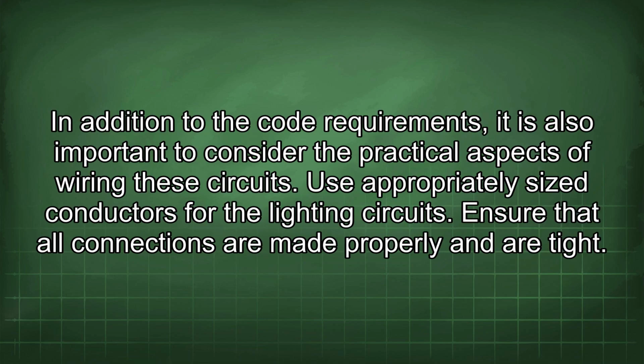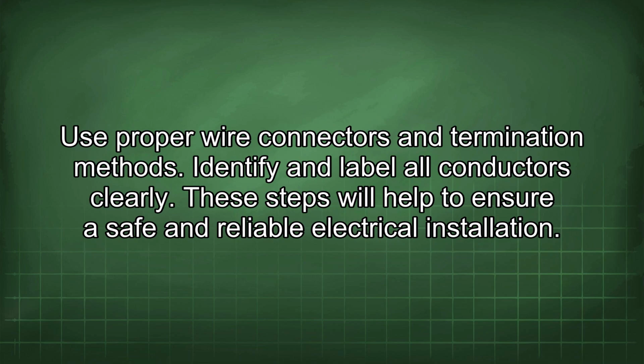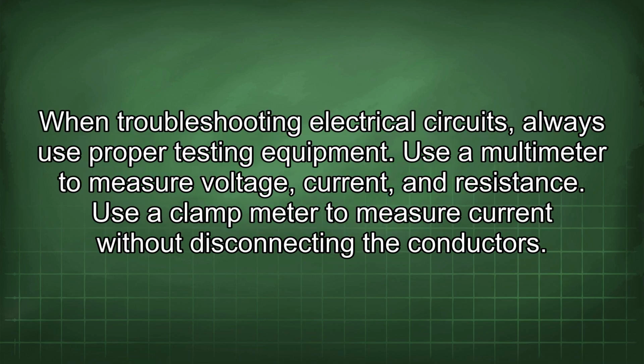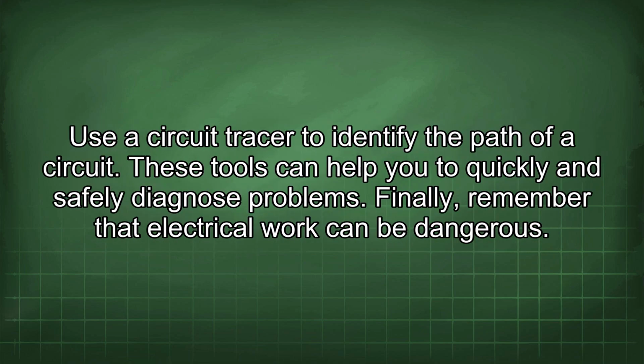In addition to the code requirements, it is also important to consider the practical aspects of wiring these circuits. Use appropriately sized conductors for the lighting circuits. Ensure that all connections are made properly and are tight. Use proper wire connectors and termination methods. Identify and label all conductors clearly. These steps will help to ensure a safe and reliable electrical installation. When troubleshooting electrical circuits, always use proper testing equipment. Use a multimeter to measure voltage, current, and resistance. Use a clamp meter to measure current without disconnecting the conductors. Use a circuit tracer to identify the path of a circuit. These tools can help you to quickly and safely diagnose problems.